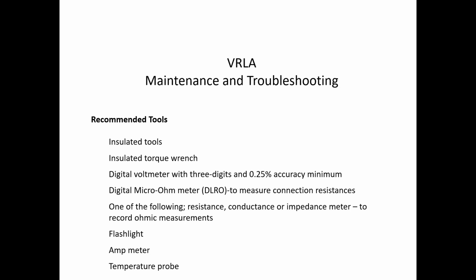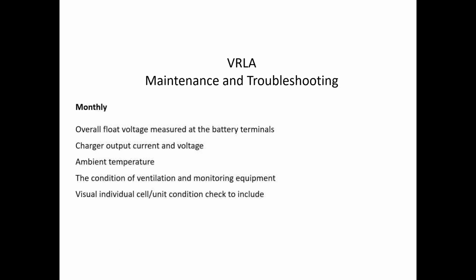We go out with a digital voltmeter. We mentioned the low resistance ohmmeter for straps. You had mentioned you're using the Biddle BITE, so that's an impedance meter. Flashlight, amp meter, and a temperature probe are pretty much what we go out into the field with when we're going to maintain a battery system and rectifier. These are IEEE recommendations. Battery manufacturers pretty much adhere to this.